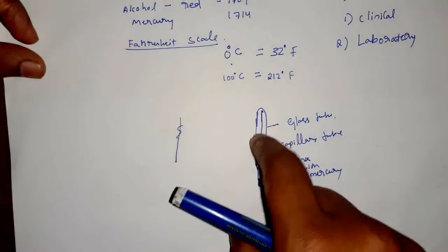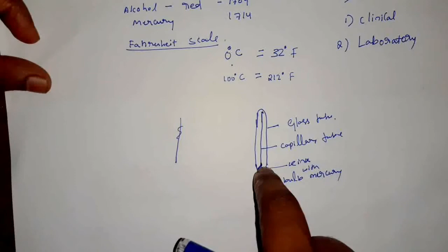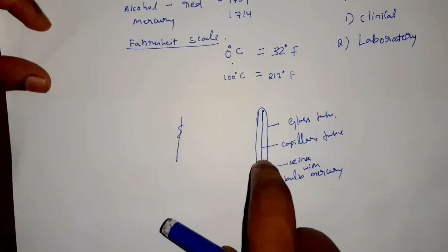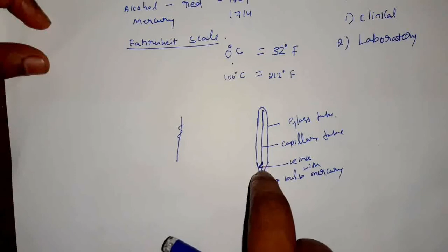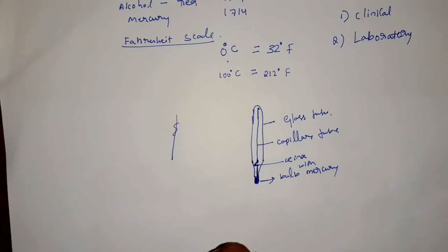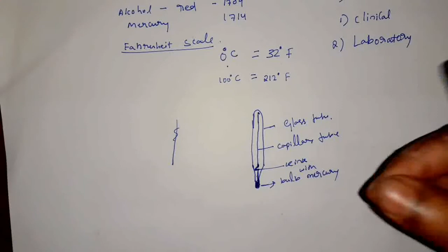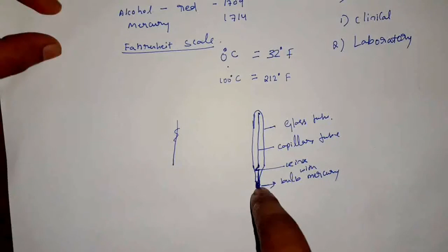So in between that gap, if this mercury line comes down, then we will not get the exact reading. Therefore, whenever the mercury rises in this capillary tube due to an increase in the temperature, it will not drop easily because of this constriction. This constriction will hold that mercury line until and unless you jerk it off. To reset this clinical thermometer, you need to jerk it 2-3 times. Then only the mercury line will once again come to this bulb.